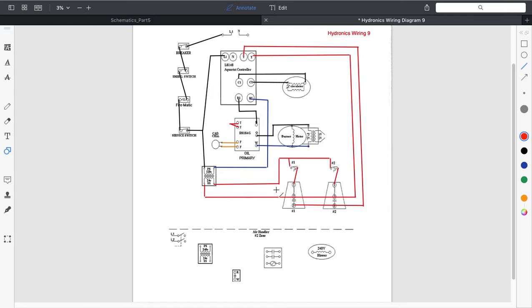But we still have the air handler hanging out there, and this becomes pretty important. Now, the air handler is being run off of this RW switch here, this set of contacts. Most likely this is going to be a pipe clamp thermostat that's clamped onto one of the pipes coming from the zone valve on 2. It's going to close as the temperature rises. But let's deal with our line voltage situation first.